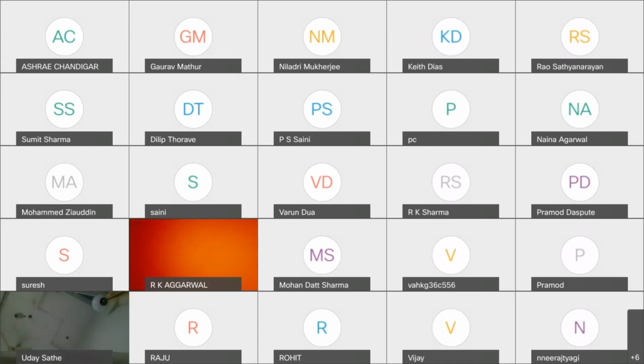Grundfos is able to achieve 0.17 as an energy efficiency index, and that is where you can see how closely the pumps adapt to the system curve changes. With respect to the other details of the pump performance, we can share the data, and we can share the details of the pumps in terms of how the energy efficiency changes over different load conditions. Okay, I hope the doubt is clear.